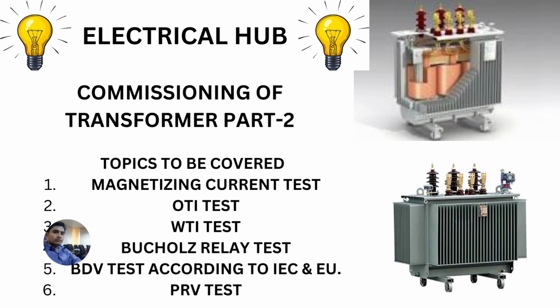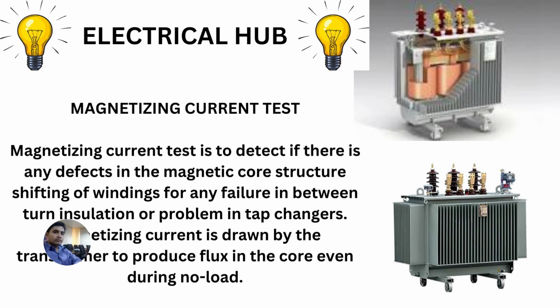Here we are going to cover the remaining topics. The remaining topics are magnetizing current test, oil temperature indicator test, winding temperature indicator test, Buchholz relay test, BDV test according to IEC standard and European standard, and finally the PRV test. Let us start with the magnetizing current test. So, why is the magnetizing current test done?